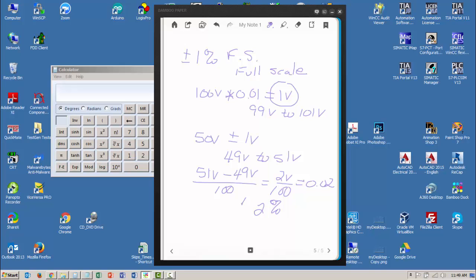So now I'm at plus or minus 2%. My error actually doubled at mid-scale, and the lower I go on that scale, the worse my tolerance is going to get.